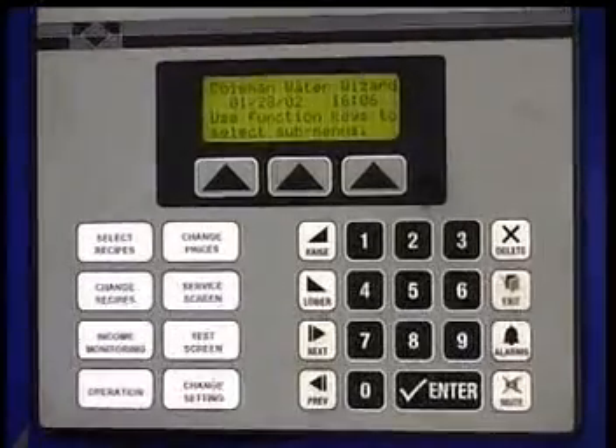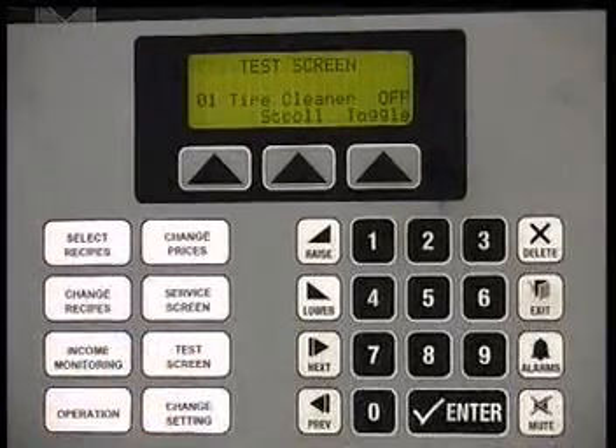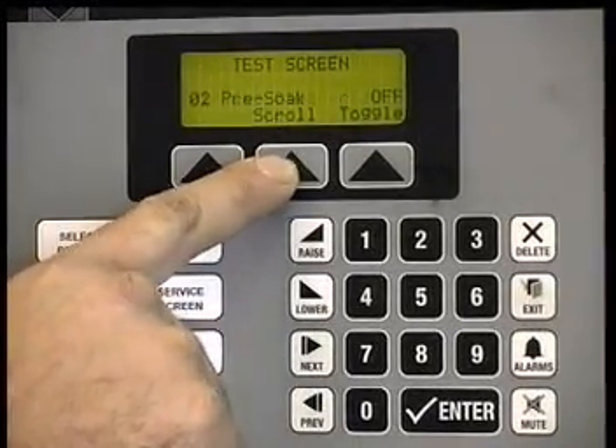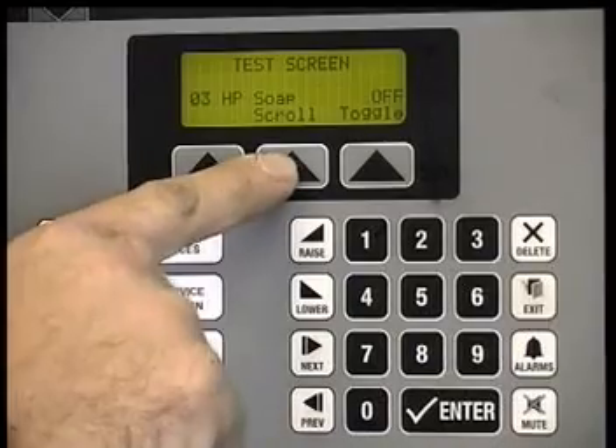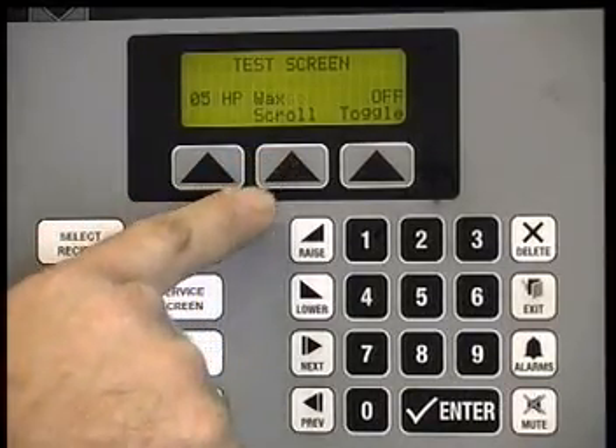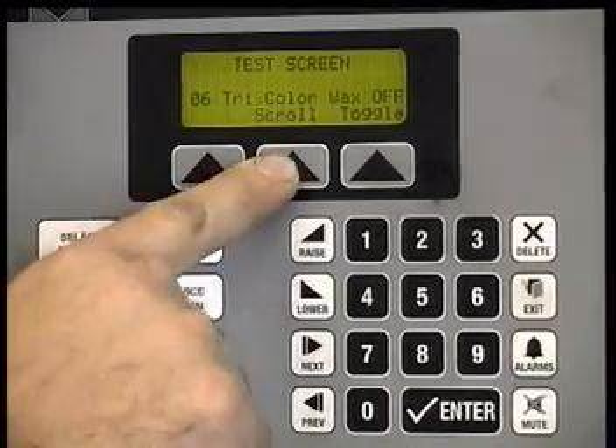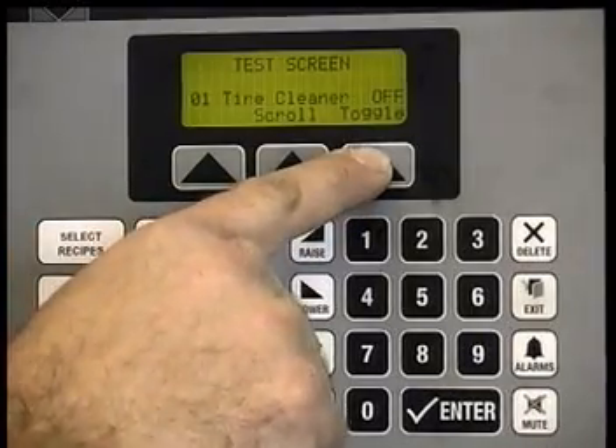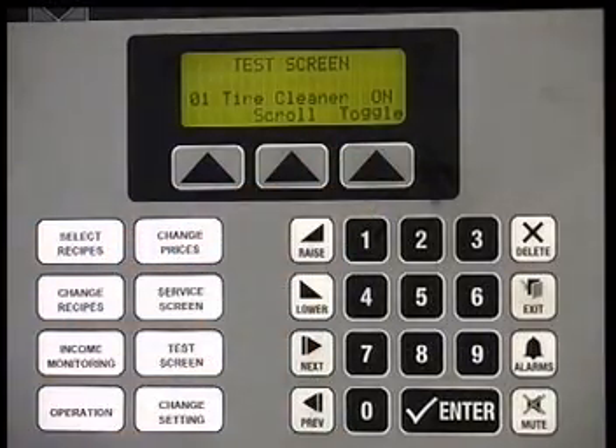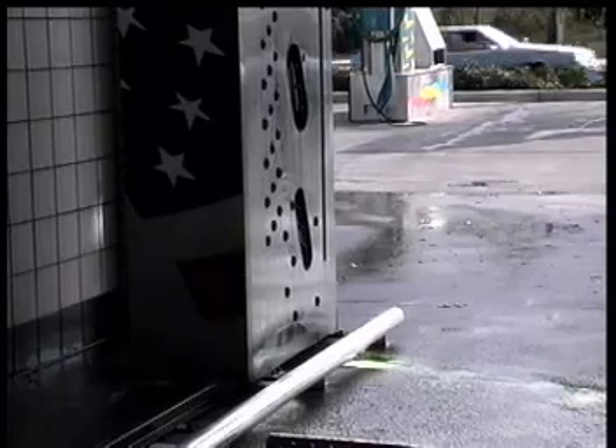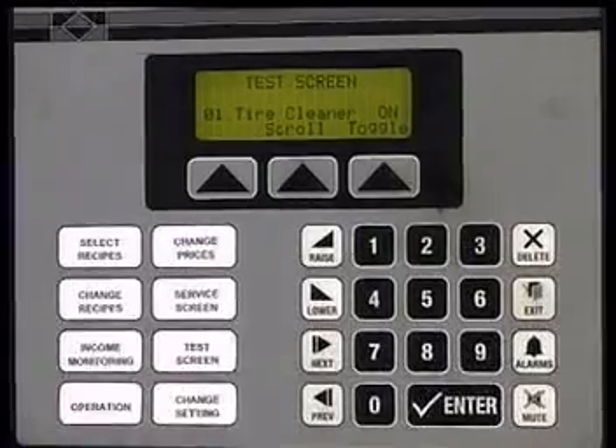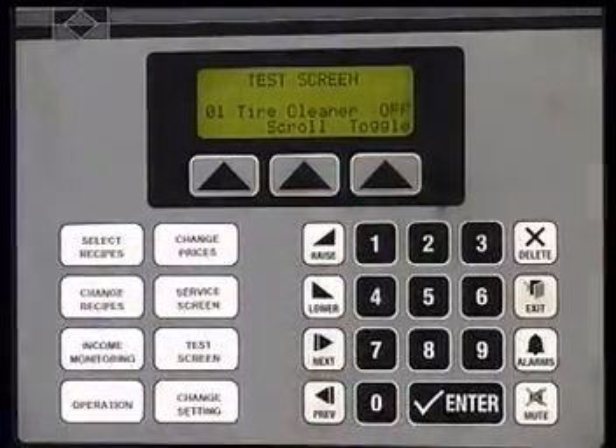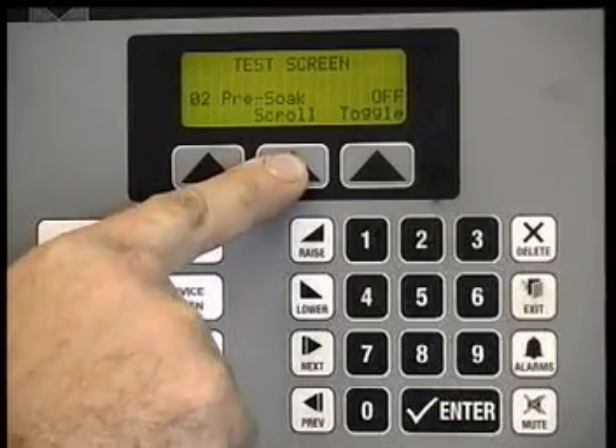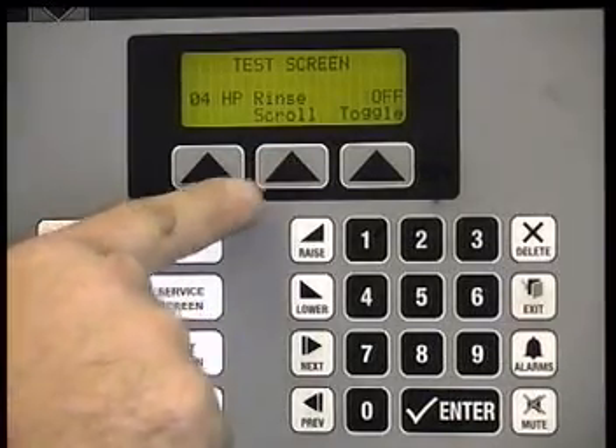The test screen will assist service personnel in troubleshooting and proper adjustment of product application. You can select the product you wish to test by pushing the scroll button until the product is listed on the screen. Once there, push the toggle button to turn that product on and off. You can then set the delivery pressure at the Procom pump or adjust the air to product mixture in the low pressure manifold box. When finished, return to the operator interface panel and toggle it off. You can continue this process with each function available to the Water Wizard.